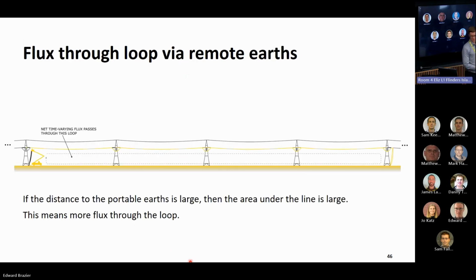So here's our loop again from a different angle. You notice that the portable earths are quite far away from the worker, in practice possibly many kilometres. Because the earths are far away, the area of our loop is very large, and a large area means a large amount of flux passing through the loop, and so a large voltage. That voltage appears between the worker and the isolated conductor above the worker's head.